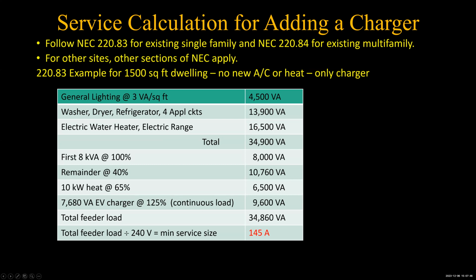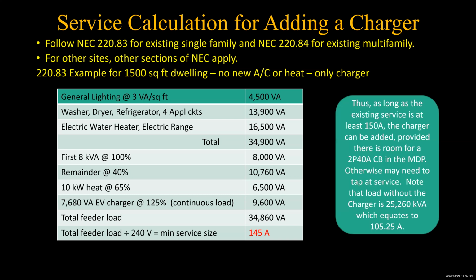So you get your total feeder load, 34,860. That turns out to be 145 amps. So terrific. If you've got 150 amp service at least, then you can put this 7680 VA EV charger in. And 7680, how many amps is that? Well, 7680 VA is essentially 7680 volt amps, or watts.